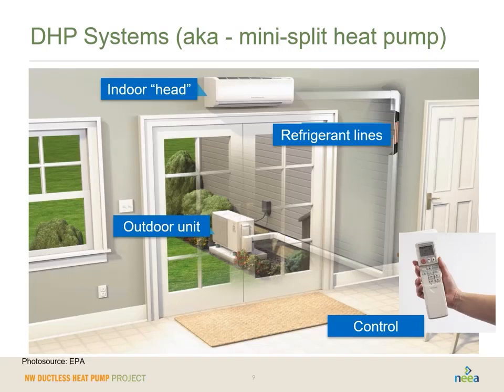With mini split or ductless heat pump systems, there are four critical components. The outdoor unit, also called the compressor, is where we're able to take heat from the outdoors, even in cold temperatures. And through the process of refrigeration, compression, and expansion, we're able to actually take heat from the outdoors, even down to very low temperatures, move it through the refrigerant lines to the indoor head, where an air movement, a fan coil, moves air over these refrigerant lines and extracts that heat back out. And the process works the same in reverse through cooling. So that's the outdoor unit.